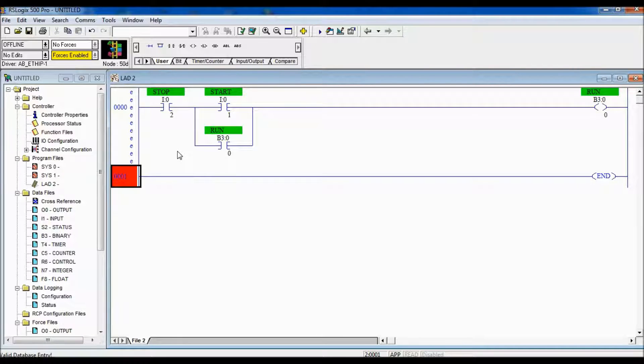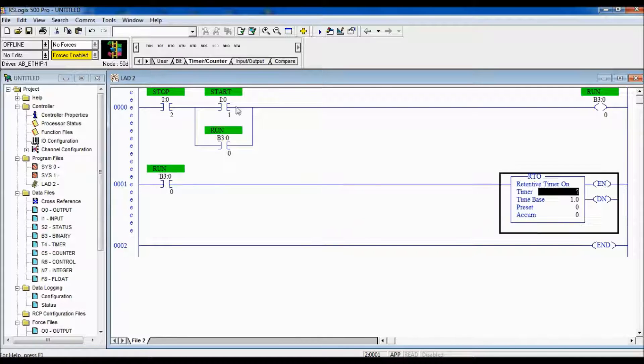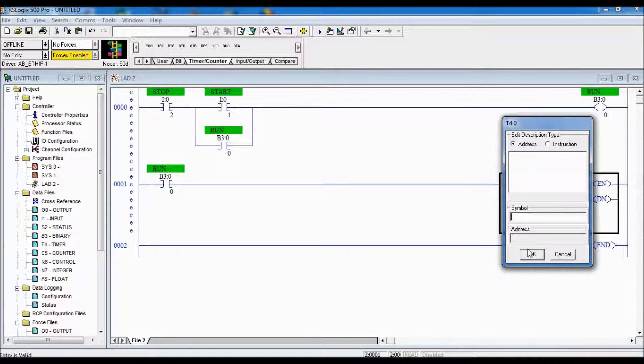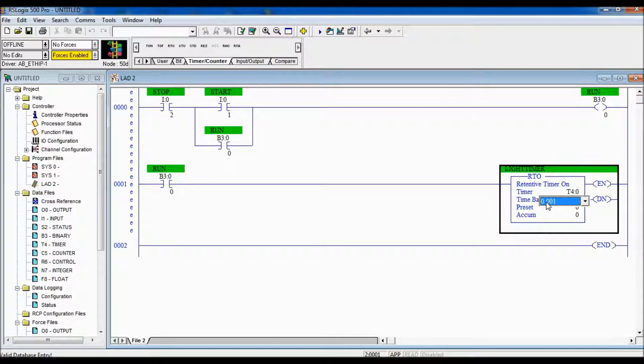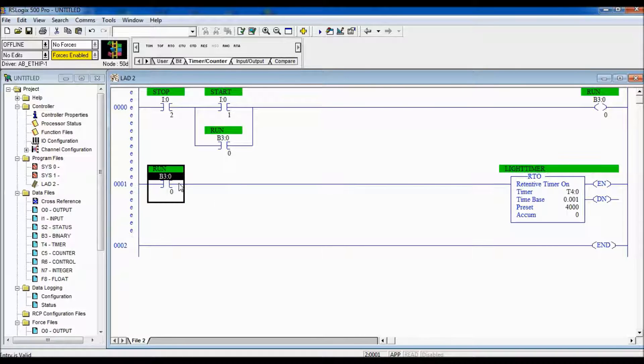Now in order to control these lights, I'm going to use a retentive timer. The retentive timer will keep count of how many seconds and will not lose its time if the logic in front of it goes false. It's going to time when our run bit is true. We need to give it a name — T4 colon zero, our first timer available. I'm going to call it 'light timer'. For the time base, we're going to put it in milliseconds and the preset is going to be four seconds. Remember, we have eight lights that come on one after another and they're each on for half a second, so that equals four seconds in total. I'm also going to stop the time when we press the freeze button.